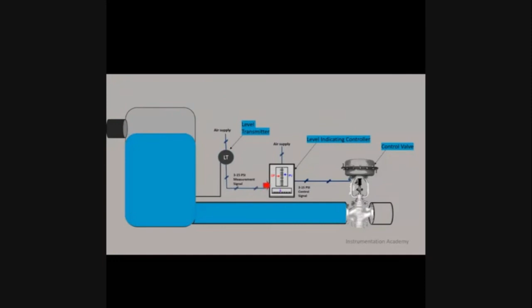The pneumatic signal now reaches the controller, here the level indicating controller. The purpose of this instrument is to compare the level transmitter's signal with a set point value entered by a human operator. The controller then generates an output signal telling the control valve to either open fully or less so that water flows out from the tank to maintain the water level at the set point. Like the transmitter, the controller in this system is also pneumatic, operating entirely on compressed air. This means the output of the controller is also a variable air pressure signal, just like the signal output by the level transmitter. Naturally, the controller also requires a constant supply of clean compressed air through the air supply tube.